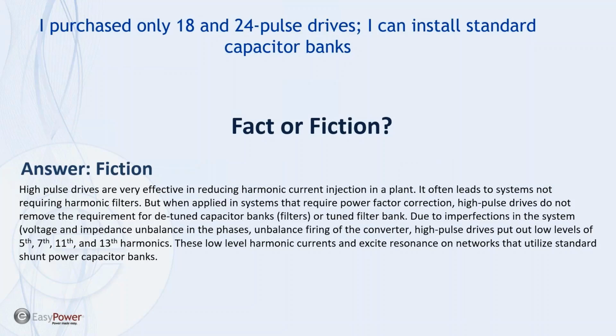I hear this all the time also: I purchased only 18 or 24 pulse drives, so I can install standard capacitor banks. So somebody goes out, they spend extra money on 18 or 24 pulse drives, and they say, well, I can buy capacitor banks now, I don't need harmonic filters. Again, simply not true.